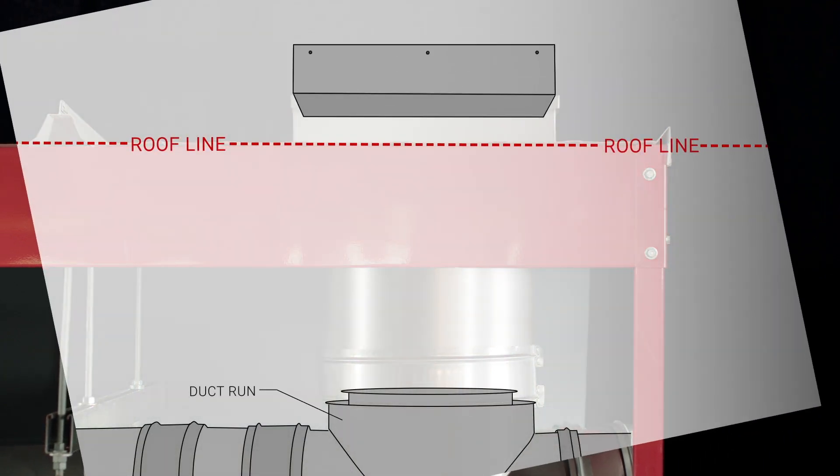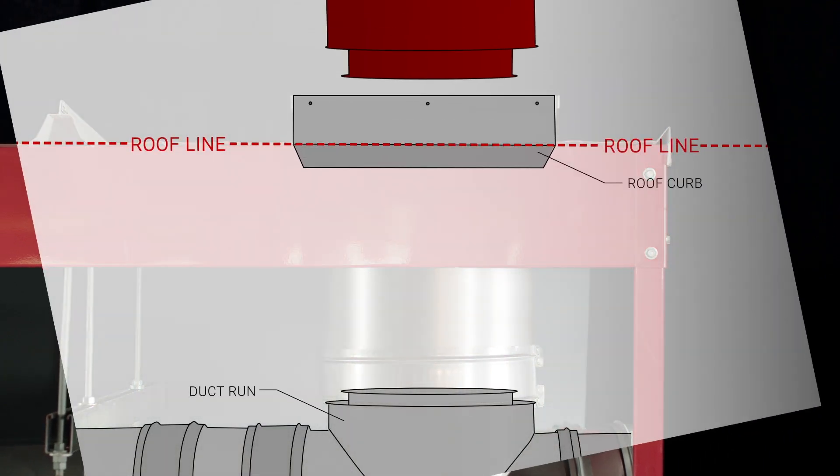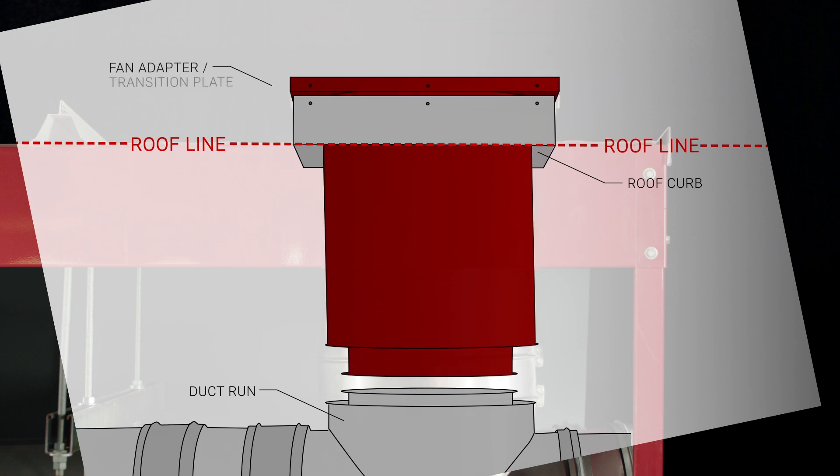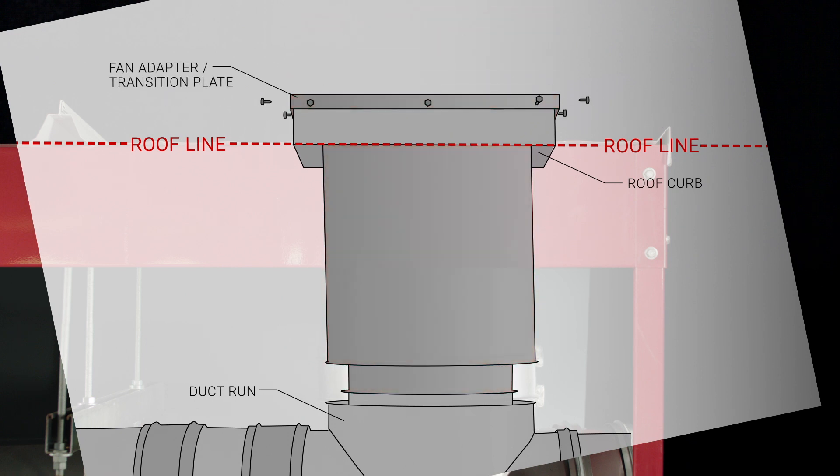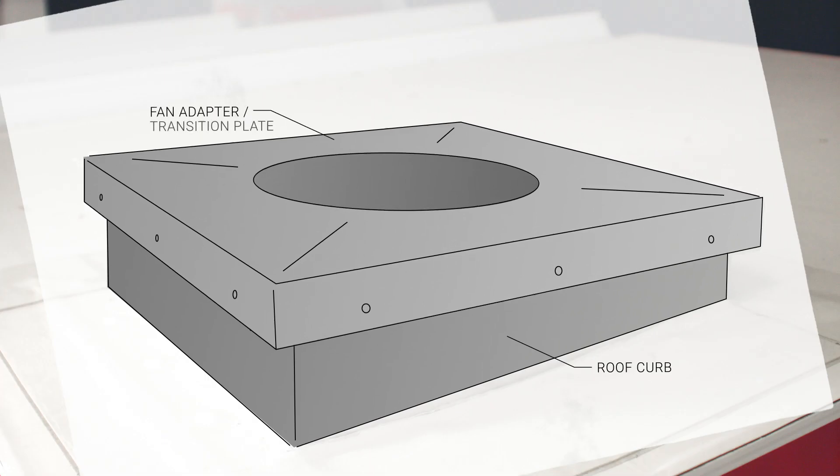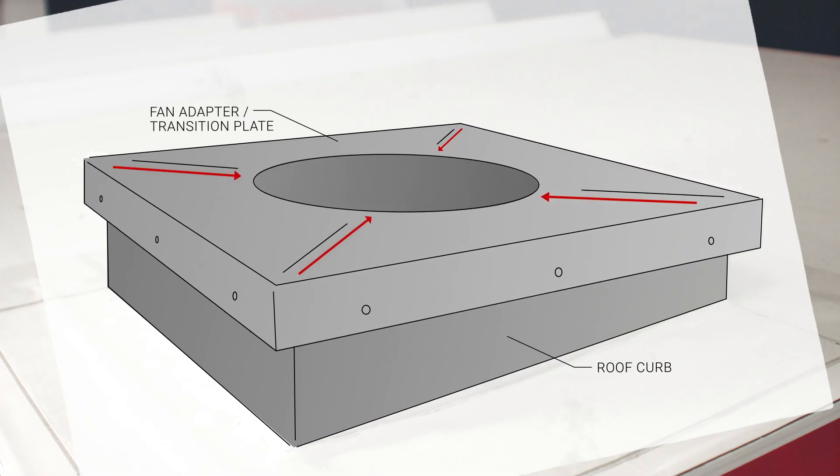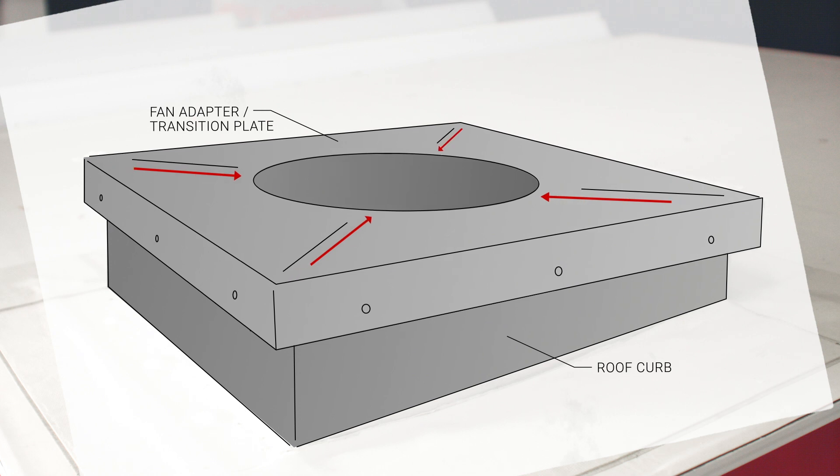The fan adapter plate or transition plate is designed to connect to a previously installed roof curb. When connected, the plate mounts on top of the roof curb, which supports the fan housing. The adapter plate is formed to provide a slope allowing grease deposits to flow back into the duct.